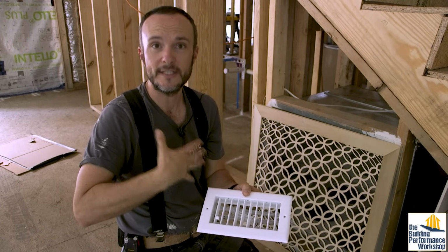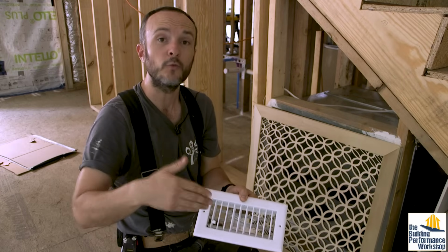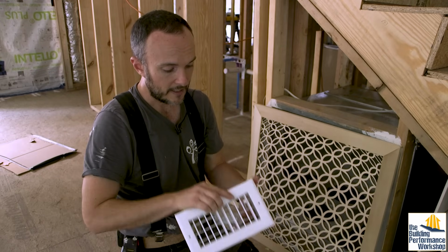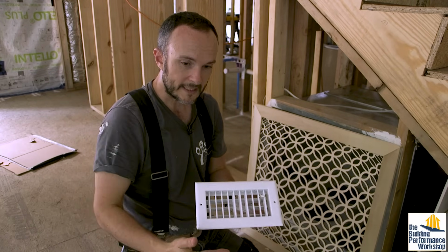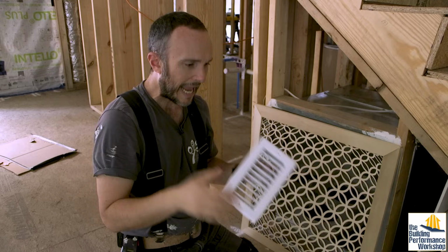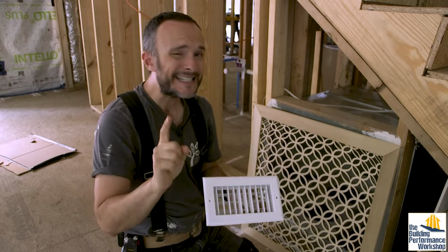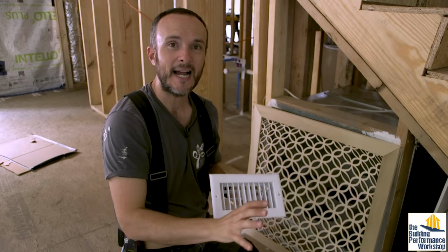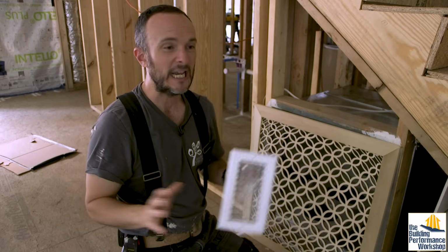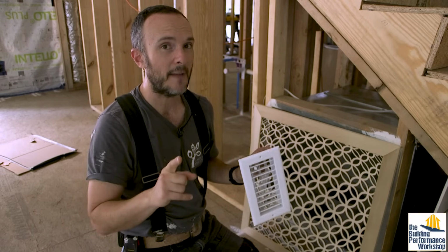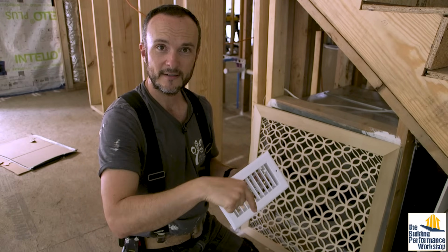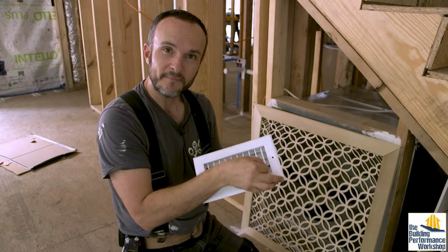What the HVAC professional is going to do when they set up the system, and I'm going to be doing this myself with the assistance of Brian Orr from HVAC School Podcast and his Kalos services team, is to run the system with all the dampers, the manual dampers at all of the branches where they come off the trunk, and all of these wide open, and just see if the duct design was so perfect that all of the duct distribution of air and BTUs is perfect without us doing anything to it, which can happen. And then, at that point, if I need to adjust things, I'll adjust the manual dampers down in the crawl space first. And then, if I need to fine-tune anything, I'll do this.